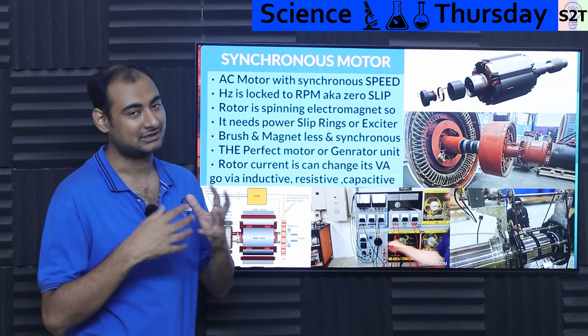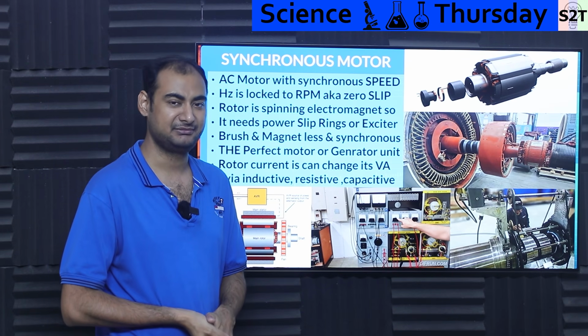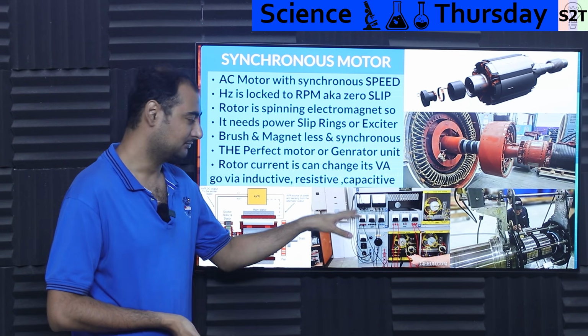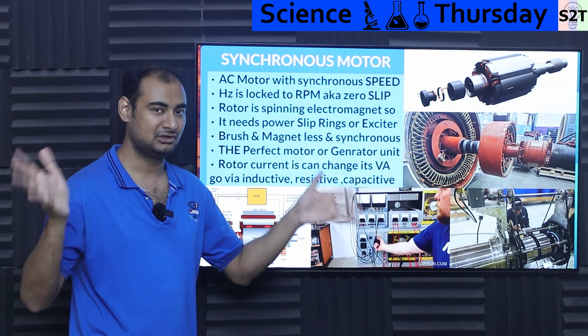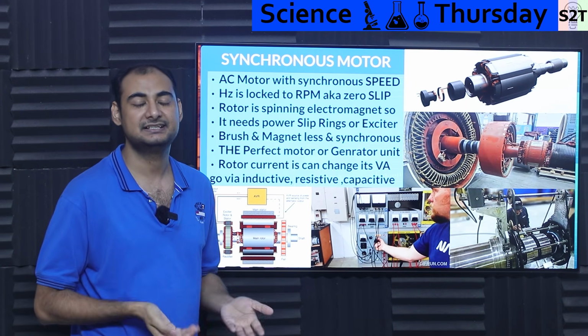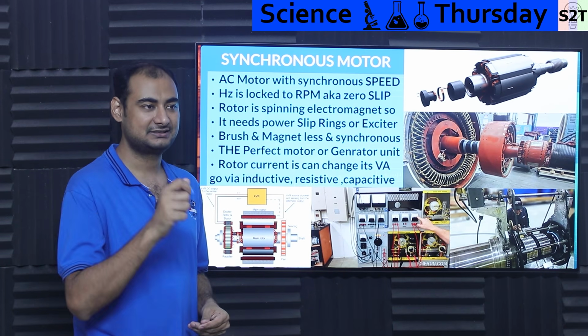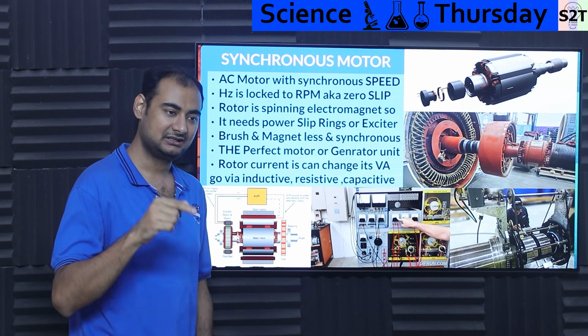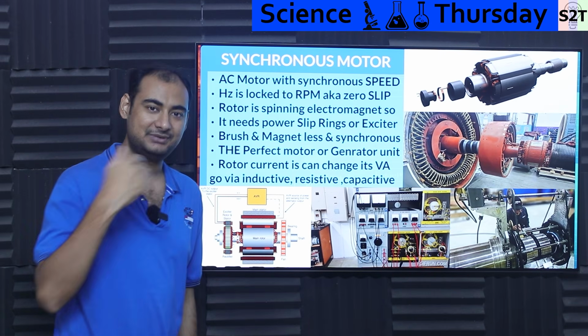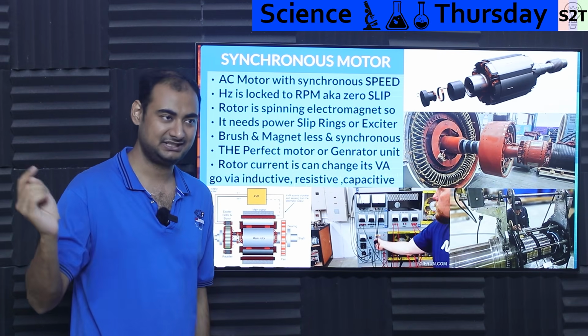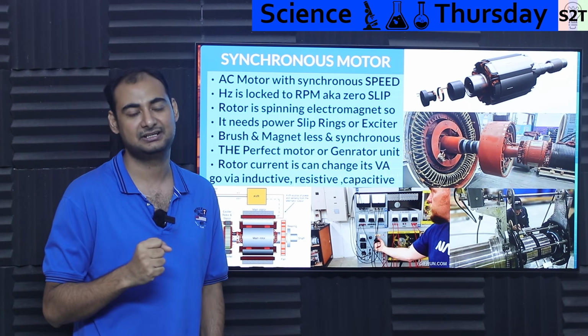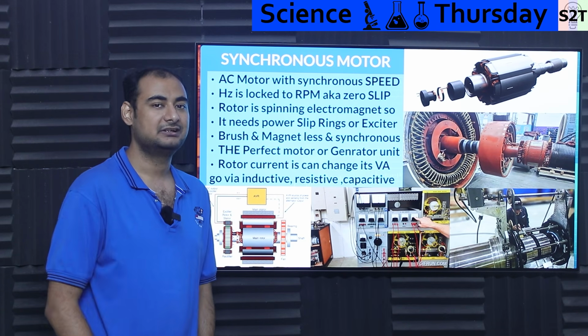Back in the old days, before capacitors became robust and reliable at the 50Hz mains signal, we used to have motors like this spinning for giant factories. What was the point? It was acting as a synchronous condenser, meaning based on the power factor it will control its rotor current, and based on that it compensates for the system, meaning the transformer that's leaching energy from the system can get a better power factor.